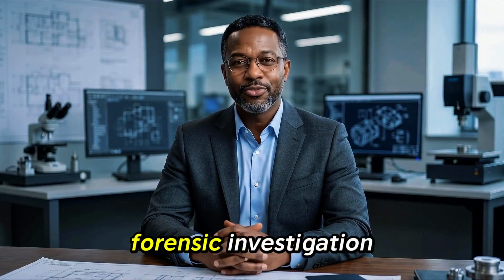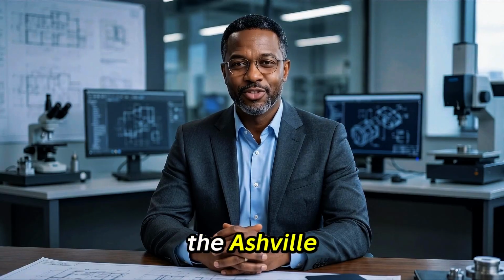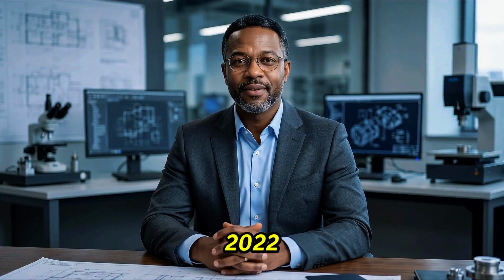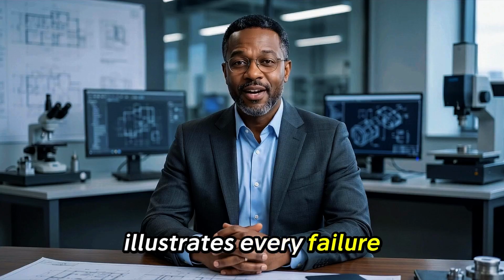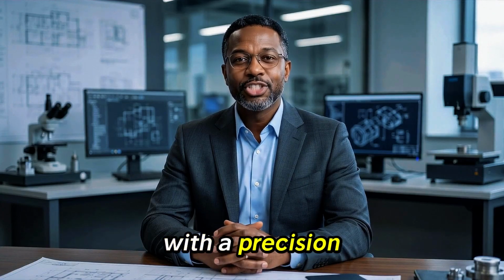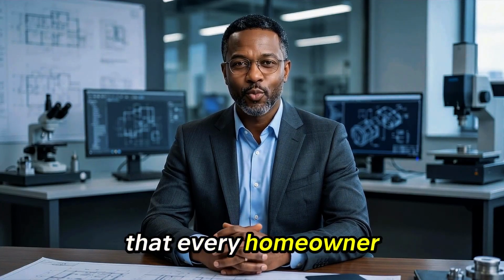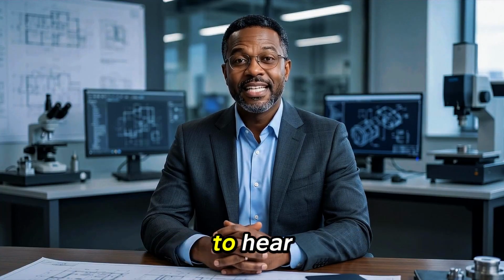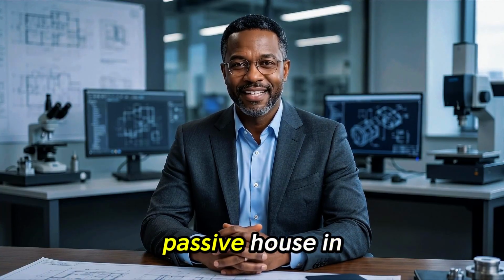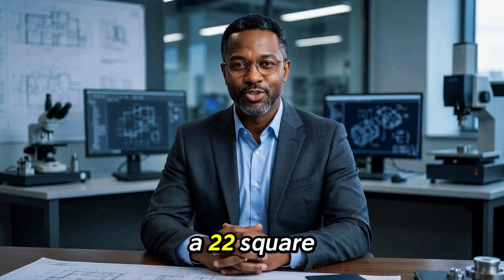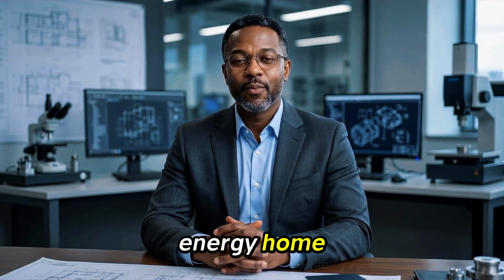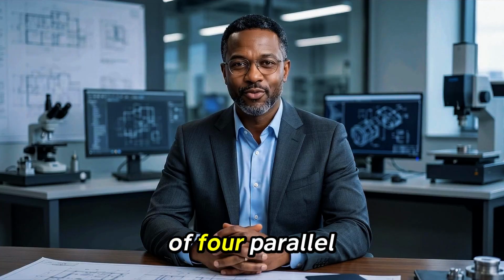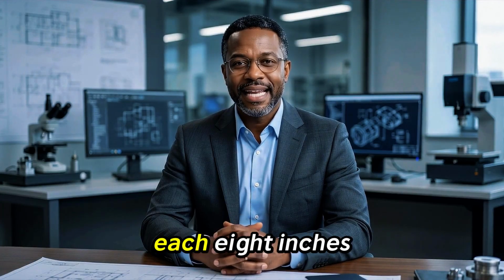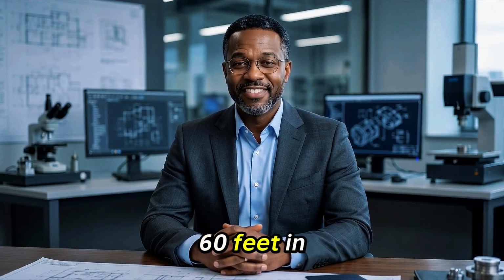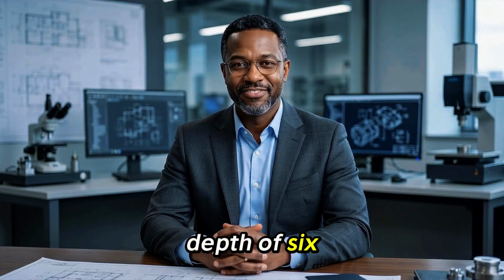Let me walk you through a forensic investigation I conducted in the Asheville, North Carolina area in 2022, because this case illustrates every failure mode I have described with a precision and a human cost that every homeowner considering an earth tube system needs to hear. The clients had built a custom passive house in 2019, a 2,200 square foot net zero energy home with an earth tube system consisting of 4 parallel HDPE pipes, each 8 inches in diameter and 60 feet in length, buried at a depth of 6 feet below grade.